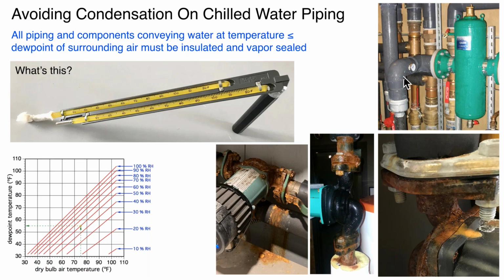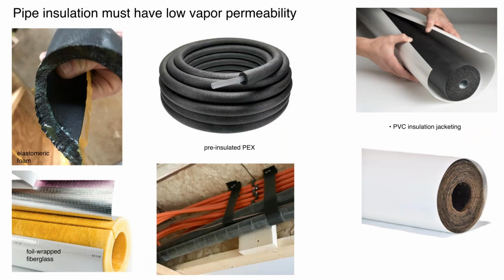tell you not to get involved with chilled water cooling systems, because not only does this create aesthetic problems, but just the dripping water can really create some major problems over time: structural, mold, aesthetic problems in the building. So how do you deal with it? Well, typically in these small systems, elastomeric foam is probably the most commonly used insulation.